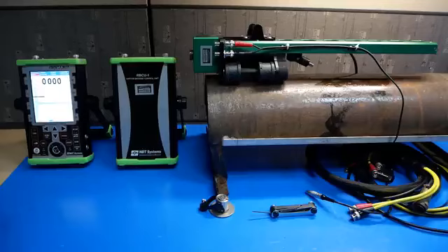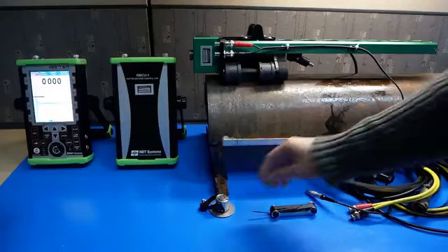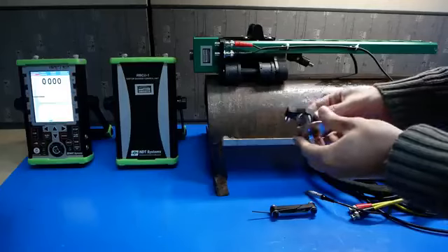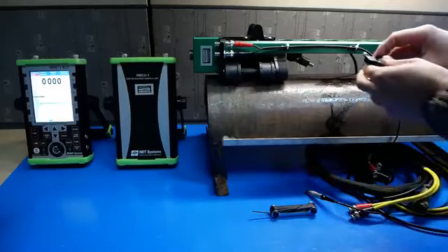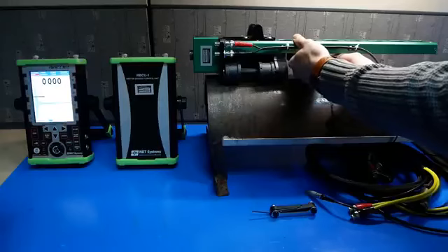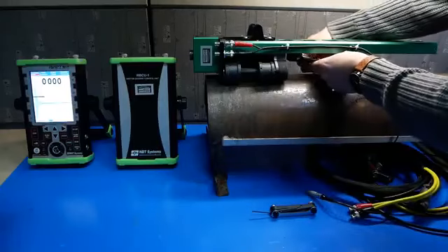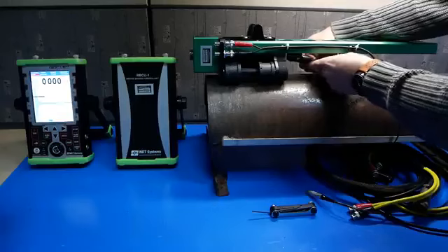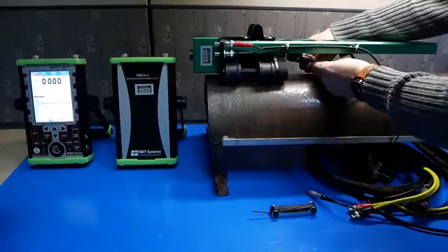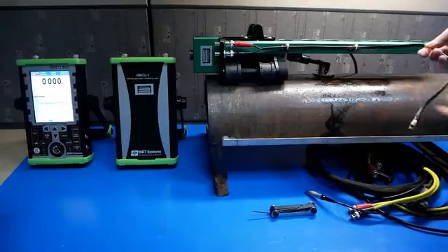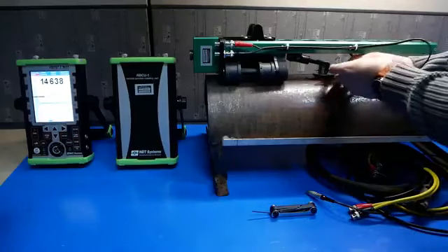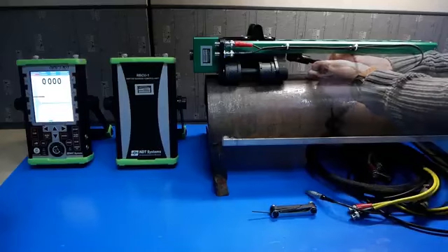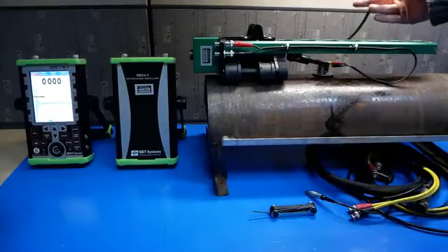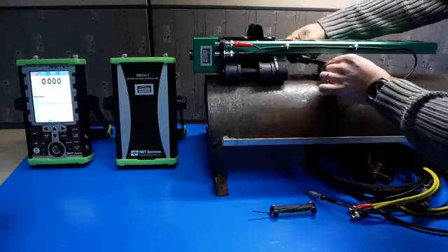Now that we've calibrated the dual element probe, let's hook everything up together and get ready for a scan. First, we'll need to put the dual element probe in a probe holder like this. Then we affix the probe holder to the scanner arm. Make sure you screw it into the detents on the arm so that it doesn't move unnecessarily. Then connect the probe cables. Then connect the couplant feed tube to the back of the probe holder.